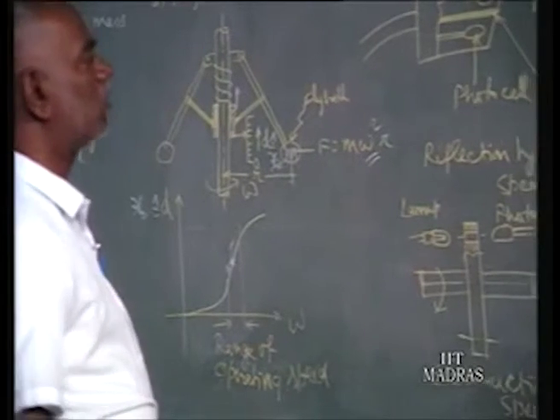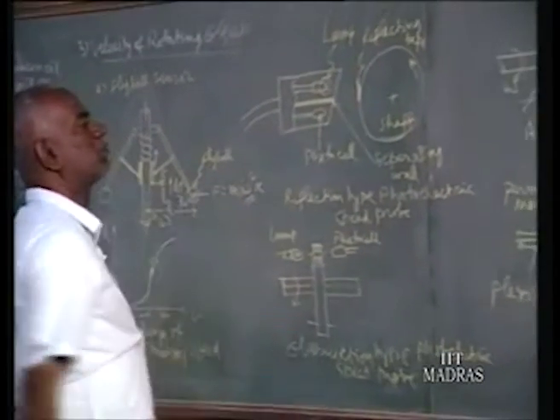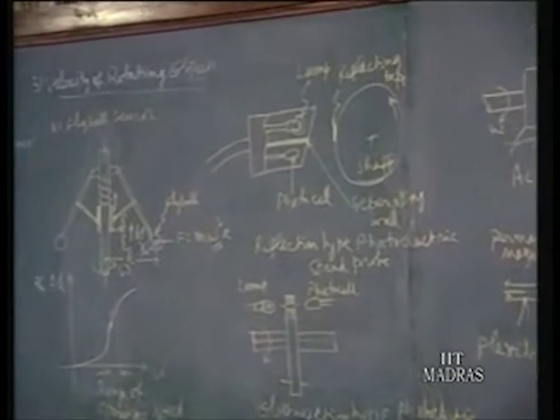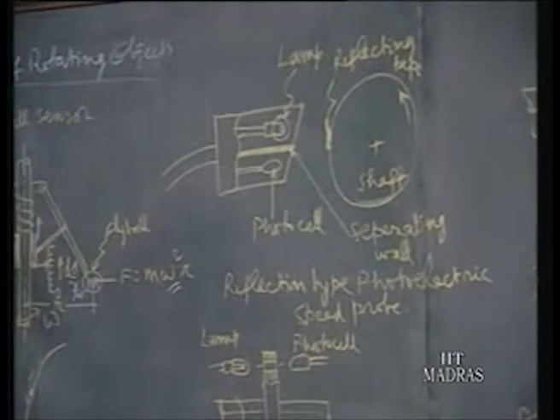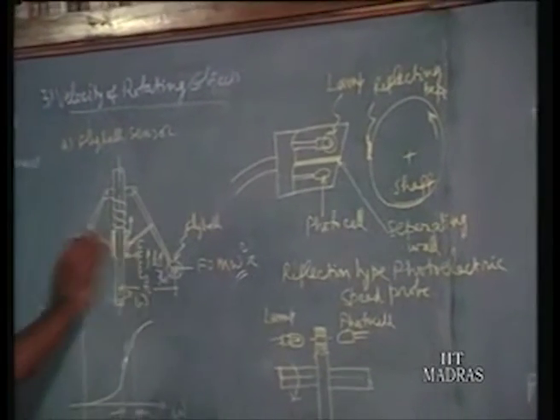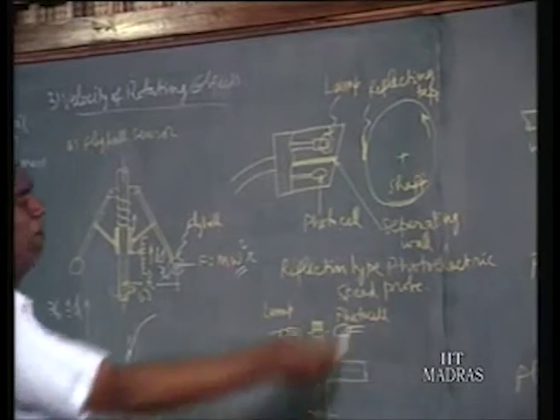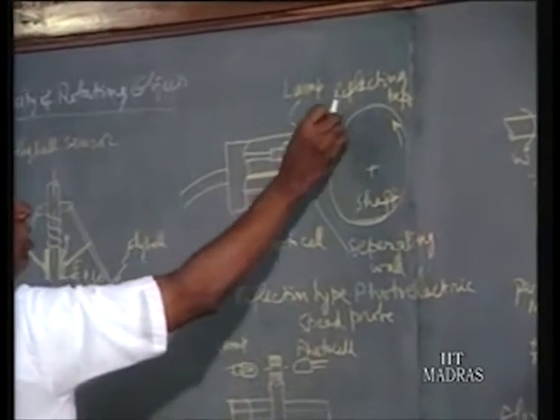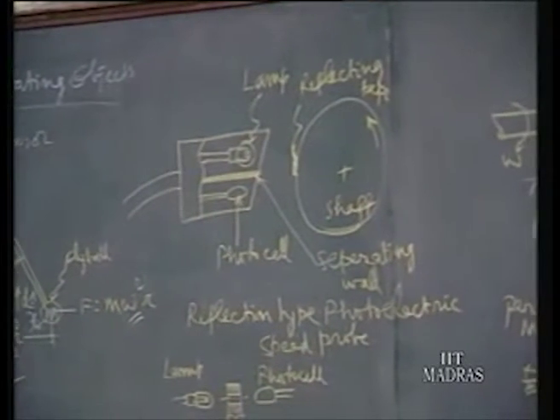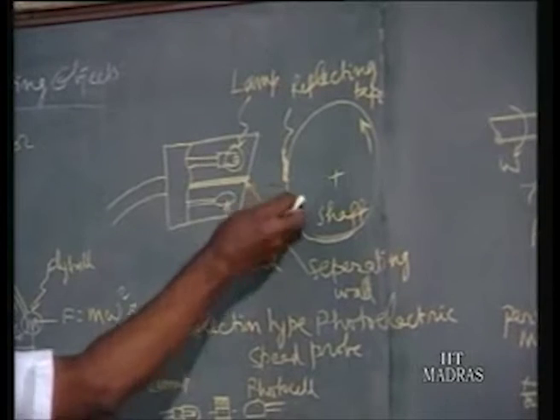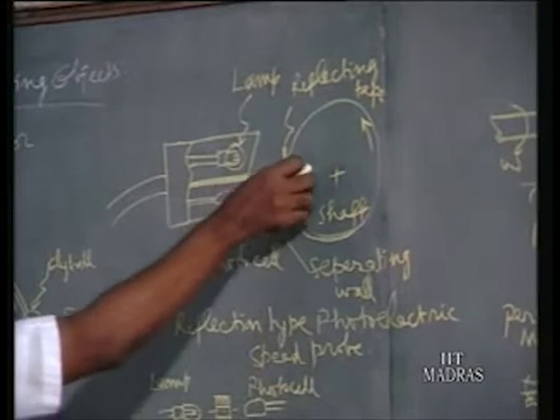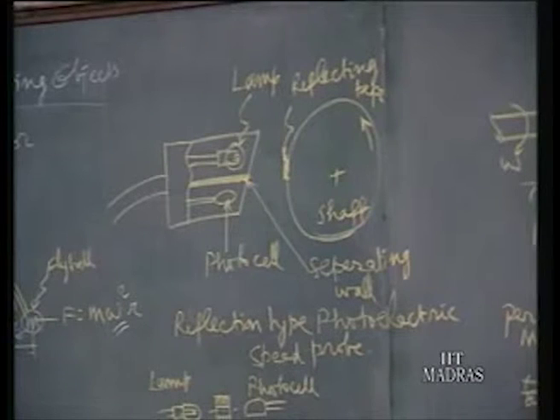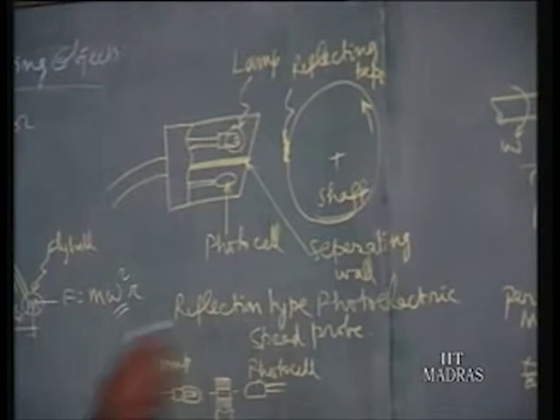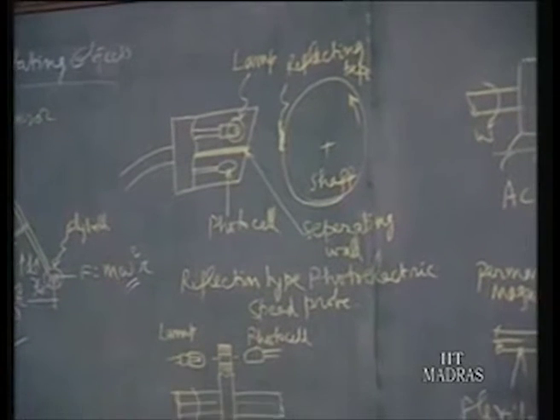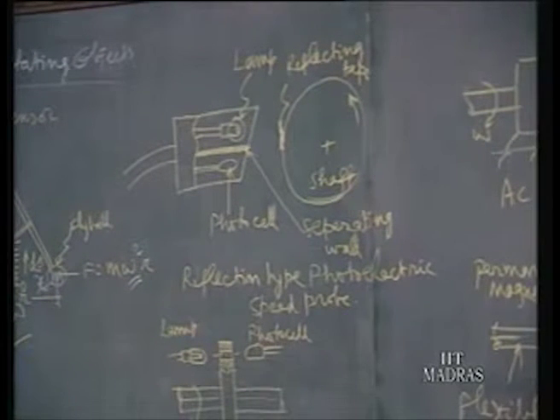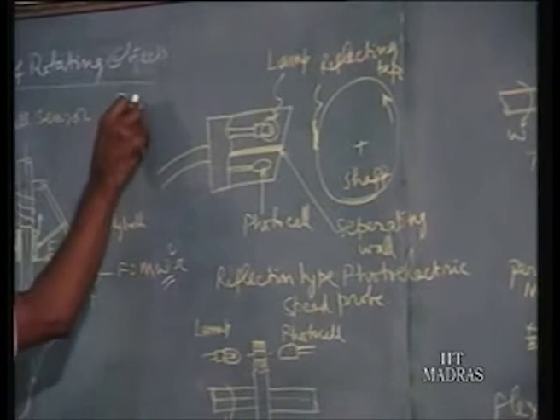And now we have got the modern methods of measuring the shaft rotation. Earlier, in the rotating shaft itself, we had connected the fly balls suitably. This is the shaft where we had connected them. But now we find in the rotating shaft, we fix one reflecting tape. This is supplied by the manufacturer. So we just cut a small piece and fix it. It will have its own adhesive. You can just paste it on the shaft. And this is based upon the photoelectric speed probe. But even before that, we have learnt this proximity pickup. We already learned proximity pickup.